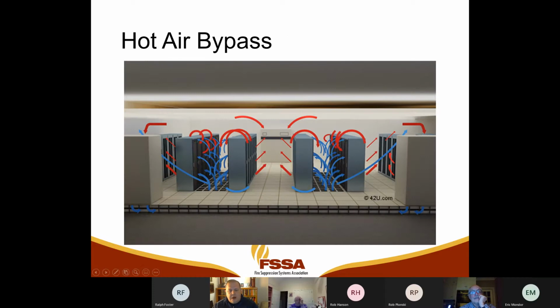One thing that happens without containment, and this is what data center operators are trying to avoid, is this concept of hot air bypass. So I blow the cold air in, it comes through, but some of that heated air, because there are fans in these, every server, every hard drive disk unit has a fan in it that's helping to blow that air through the unit from the cold side to the hot side.